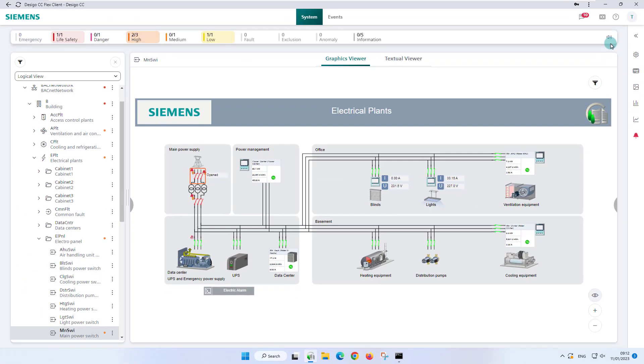Finally, this button indicates the status of the buzzer. The buzzer is the sound emitted by a client station to notify the operator of events in the Flex Client application. If a site has multiple client stations, each one will emit its own sound. When a new event occurs, the client station emits an audio alert that continues for as long as that event remains unprocessed. If there are multiple incoming events, the buzzer continues to sound for as long as they remain unprocessed. The buzzer stops when the incoming events have been acknowledged.